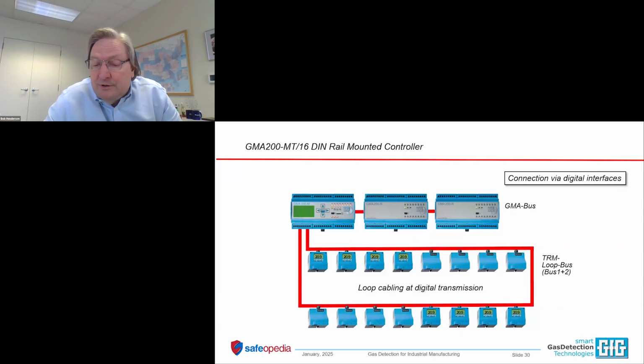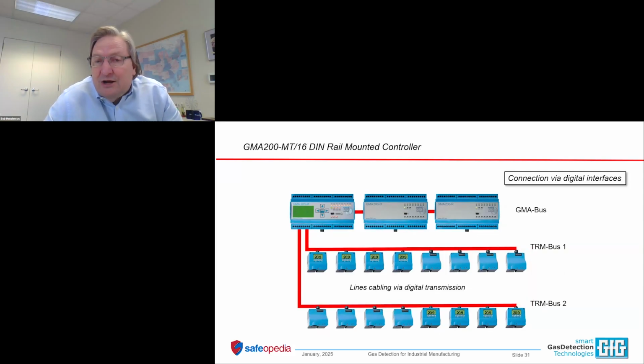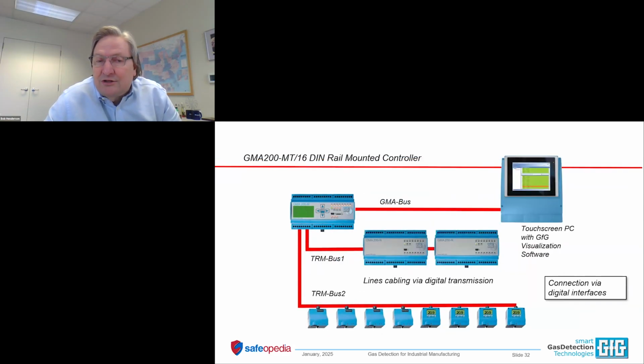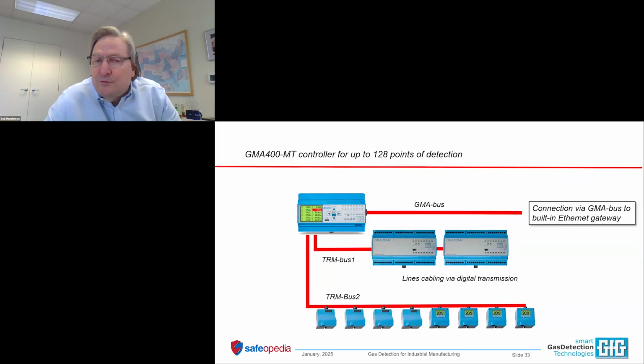And you also have the option, instead of using an independent hardwired connection for each transmitter, to use digital communication means to put every one of the transmitters on a common bus line. Here would be an example of that. The controller has 2 bus lines plus a third bus for the system, and you can easily build amazingly complicated systems and scale the system up as large as it needs to be just by using these digital communication methods. And from the controller, you can always take that information for all of the transmitters in the system to a central computer or PLC.